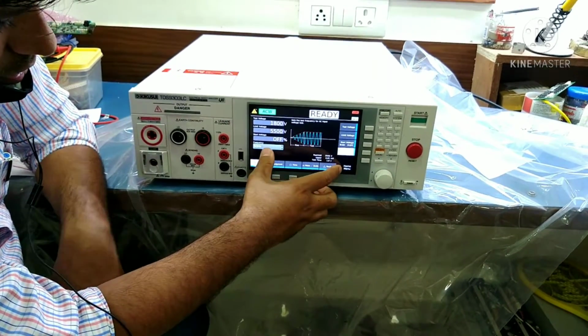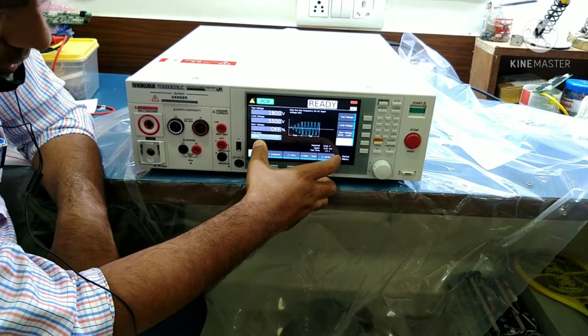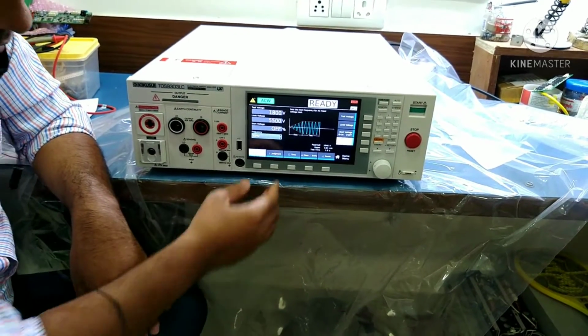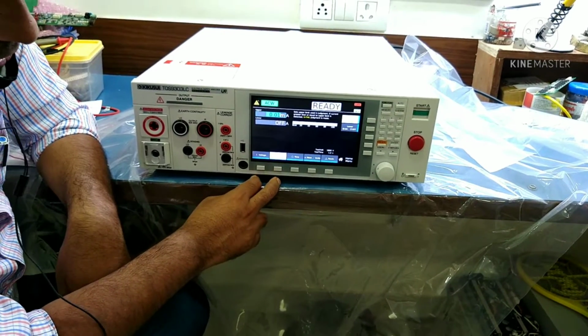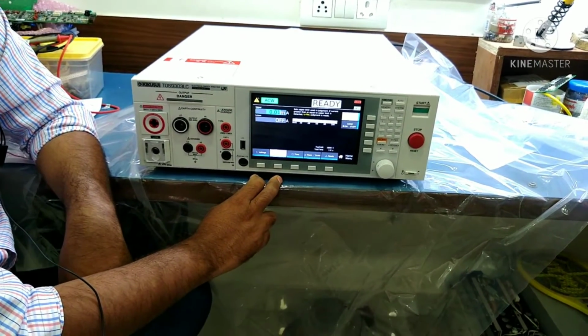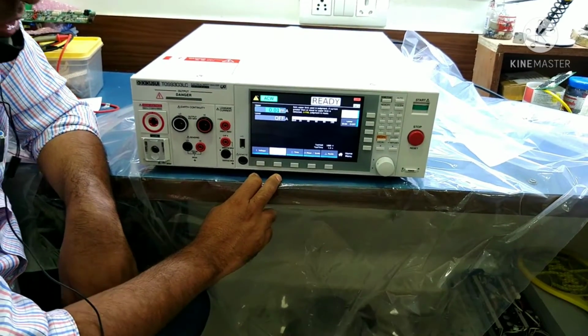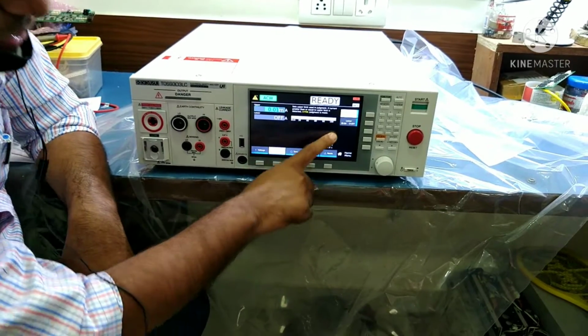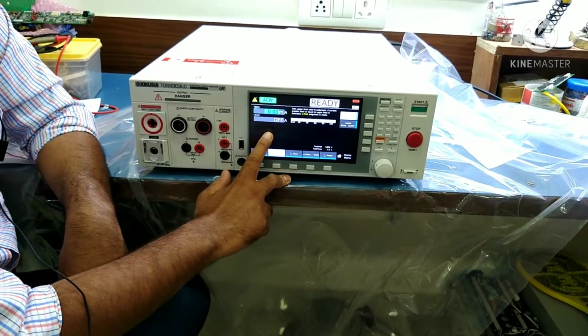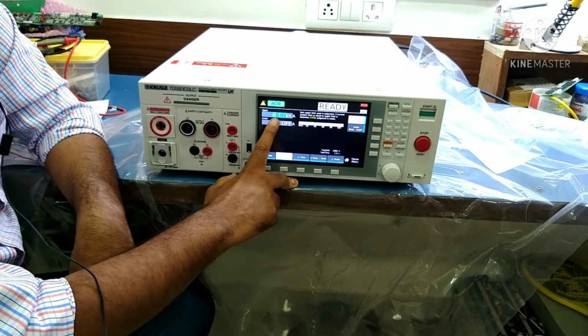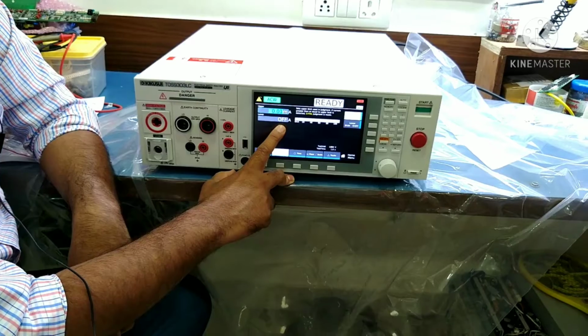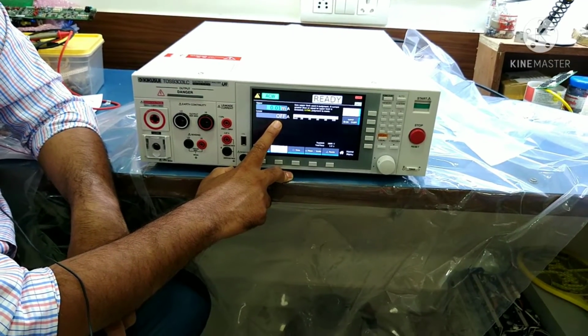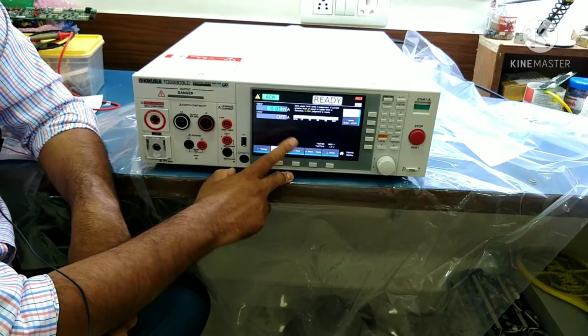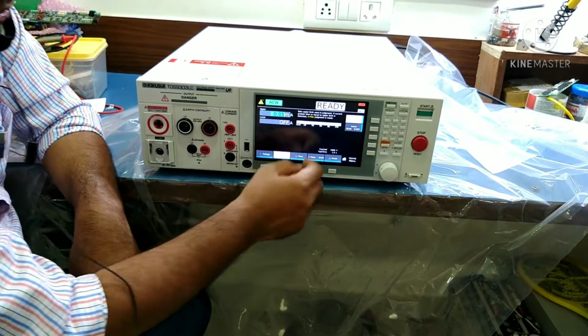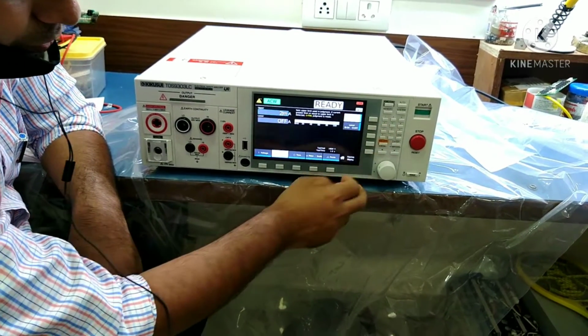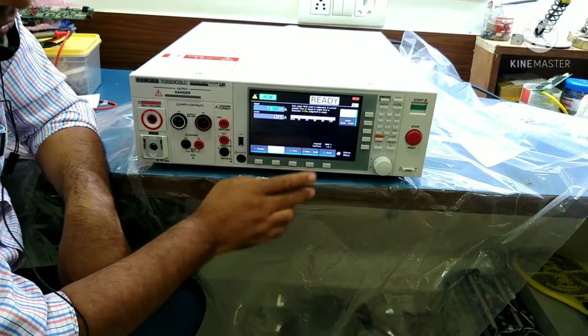This is the frequency. This is the Indian standard frequency, that is 50 Hz. You can change it to 50 Hz or 60 Hz if you are using it outside India. This is the judgment setting. Here you set the leakage allowed for any DUT, device under test. You can set the leakage up to 100 milliamps. Generally we set the leakage in the upper value, and the lower value will be off. If you switch on the lower as well, it will only pass values that fall between the lower and upper values. So I am going to set 2 milliamps and press enter. Now it is set to 2 milliamps.